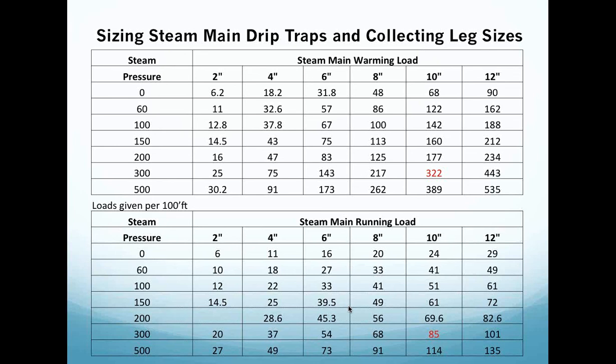And I need you to know that the actual warming load at 300 psig, which I just chose as an example, a 10-inch main is going to actually produce 322 pounds per hour of condensate per 100 feet. So I have been to a lot of plants, and I have asked folks if they use main steam line drip traps, because I can't see any. And I'll walk their plant, and I won't see any steam traps located on their steam main. And I need you to know your steam mains at running load and at warming load are going to produce condensate. And it's going to be up to you to evacuate that and make sure that you don't allow that steam to converge with that condensate inside that space or system.